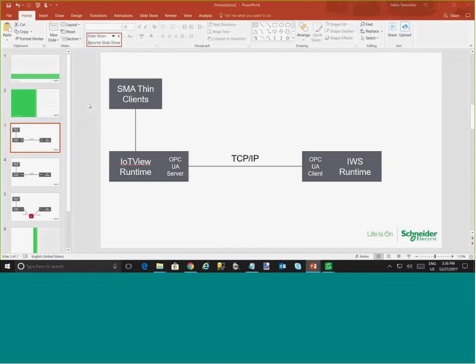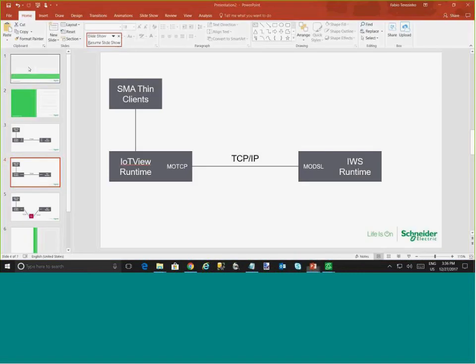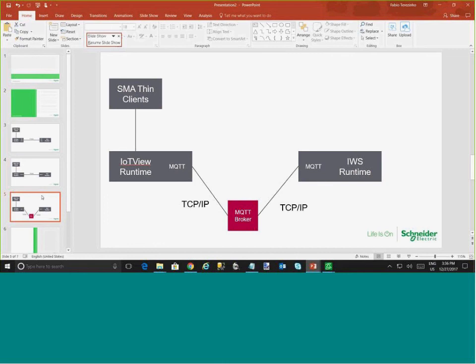And via Modbus, when you use Modbus TCP, you control how fast you want to poll data. If you use the option enable read when idle, it is as fast as possible. If you use read trigger, then it's as fast as the tag in the read trigger changes value. And MQTT is all immediate, based on subscription and publishing. So hopefully it addresses your question there.